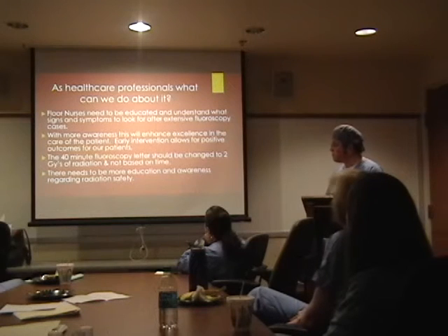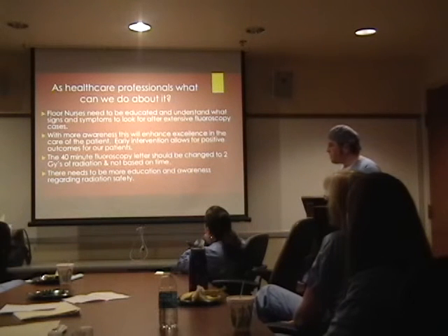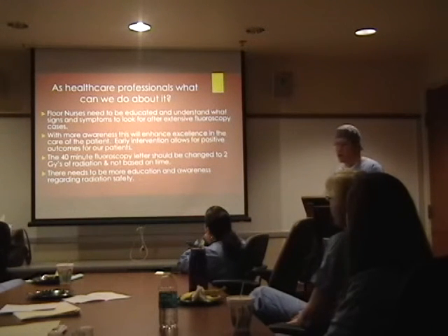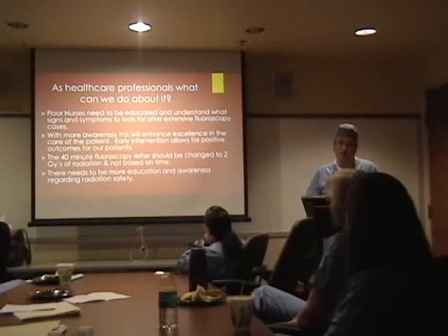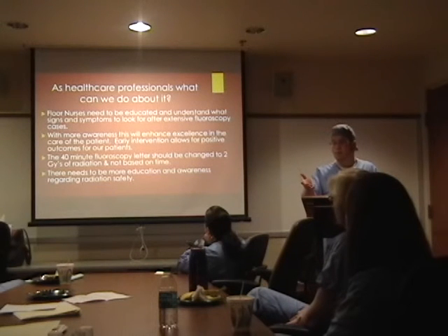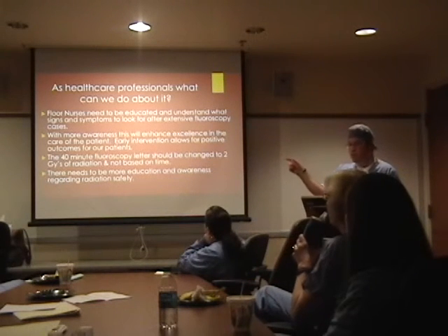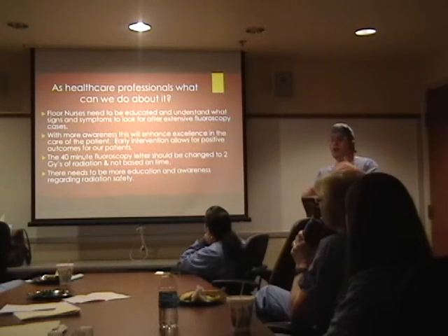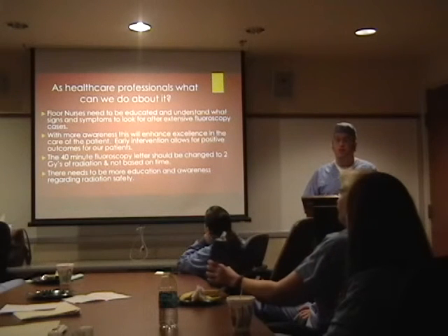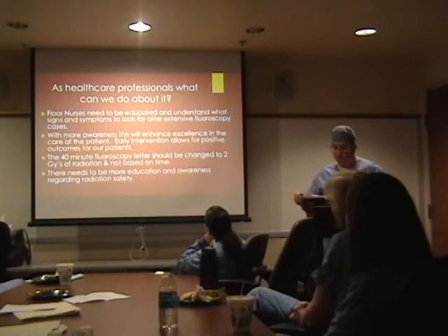Like I mentioned before, the 40-minute fluoroscopy letter may not be the correct way of going about this. So why not change it to 2 grays of radiation and not base it on time? Because you may be working on a leg, and again, watch your AKs and your dosage rate. Working on a leg, it may be like 5, 6, because you're not going through that much tissue. Whereas your chest, you have to go through a lot of tissue in some cases.